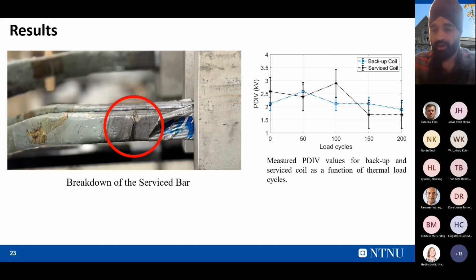So this will give an idea of how the PD values and the tan delta values give an indication before the failure of any insulation, any hydrogenerator stator insulation.